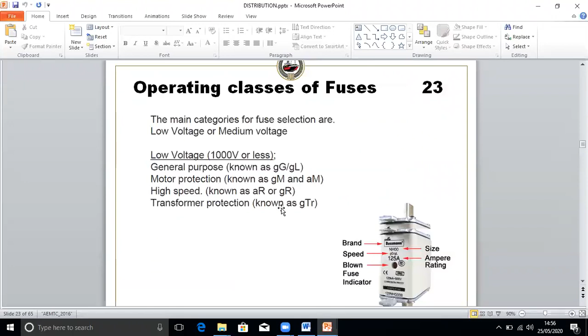Look at this fuse here now. In this fuse, you will find a small g and a capital G. This is a general purpose fuse. This is the brand name, this is the speed, how fast it operates. And this indication shows whether it is blown or not. If it is blown, it will pop out. This shows the ampere rating, 125 amps. Voltage is given here, 500 volt, so you can use it up to 500 volt. This type of fuse has a special puller. You have to put it on this and pull it out.